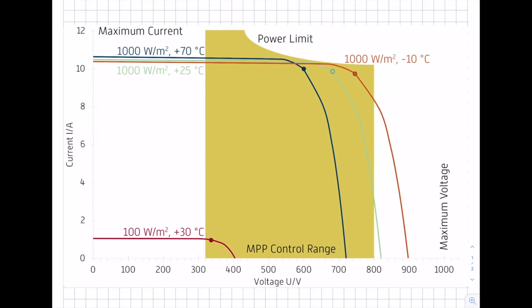We also check what happens under different conditions. The blue curve is at 1000 watts per square meter irradiance and a module temperature of plus 70 degrees Celsius — a typical situation on a hot summer day. As module temperature increases, the voltage of the PV modules decreases, and the MPP also decreases. But the MPP must still be within the yellow marked MPP control range of the inverter.